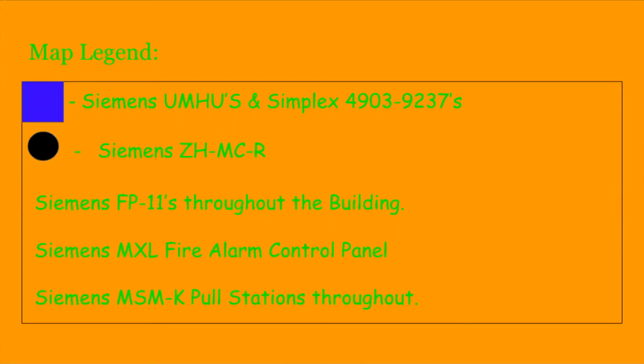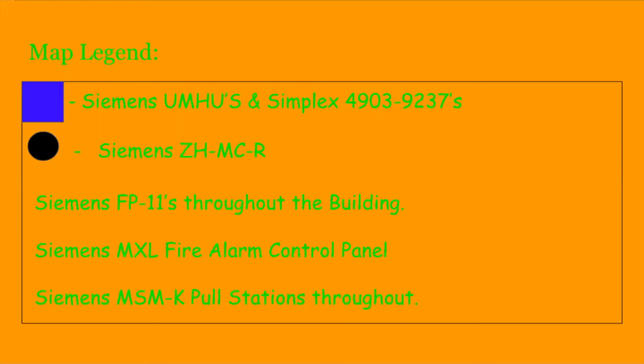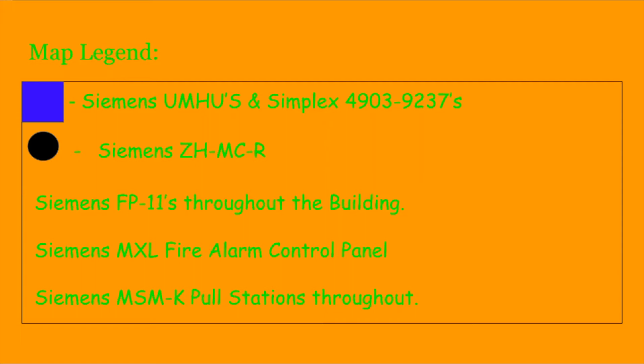And for the little black dot right here, this is a few devices that were replaced for this system. And that is the Siemens ZH-MC-R replacing a few things. Throughout the building, there were FP11s. That's pretty much all the smoke detectors they did have. The main fire alarm control panel was a Siemens MXL fire alarm control panel. This one was not voice-evac, it was just a regular panel. There was Siemens MSM-K pull stations throughout along with some Simplex pull stations in the newer Simplex section.